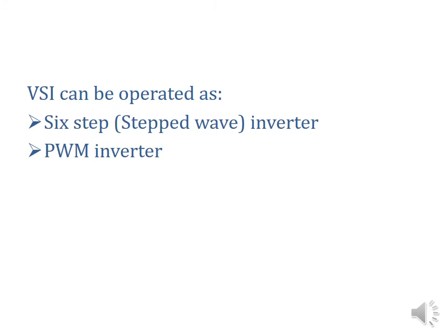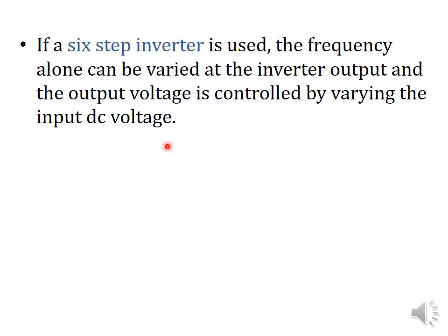Next, let's see how the voltage source inverters are controlled. It can be operated as either a six-step, that is a stepped wave inverter, or a PWM inverter. If a stepped wave inverter is used, then the frequency alone can be varied at the inverter output. That means the six-step inverter is capable of varying the frequency only; it cannot control or vary the magnitude of the output voltage.